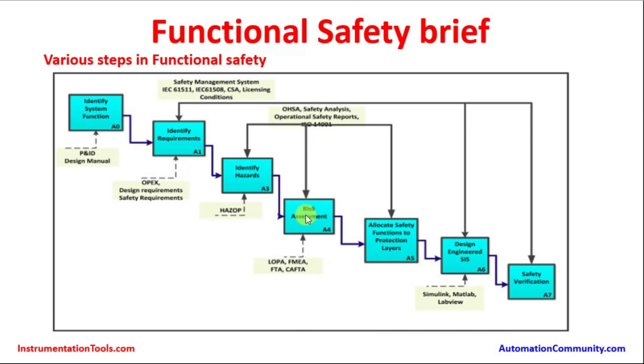Using this, risk assessment has to be performed by the team. Process safety personnel and process operation personnel — having thorough knowledge of the process and what kinds of risk can happen in the plant — must be able to identify any hazards. In this step, LOPA (layer of protection analysis), FMEA (failure mode effect analysis), fault tree analysis, and a combined fault tree matrix are required. All these analyses are done in the risk assessment stage.